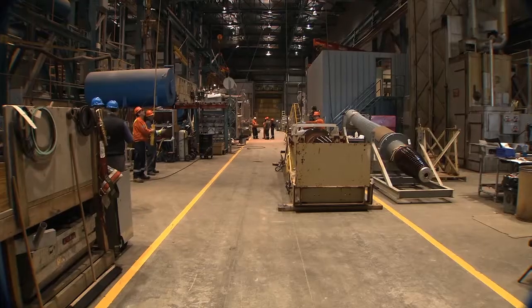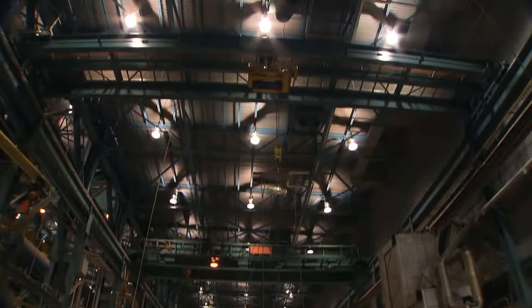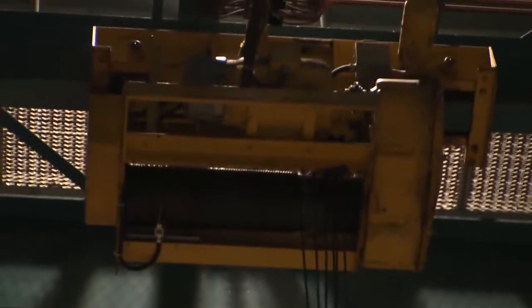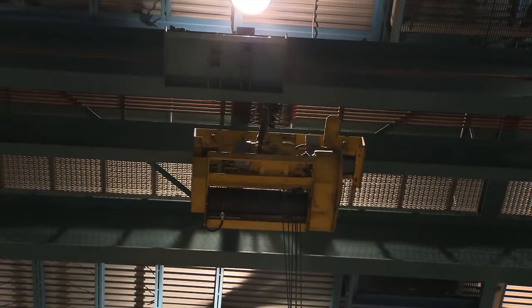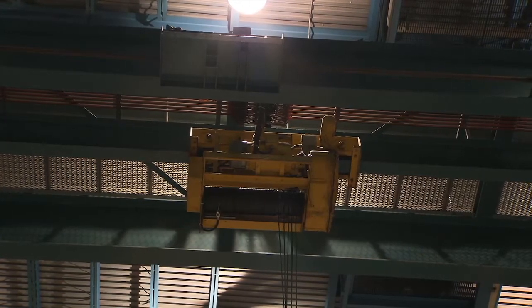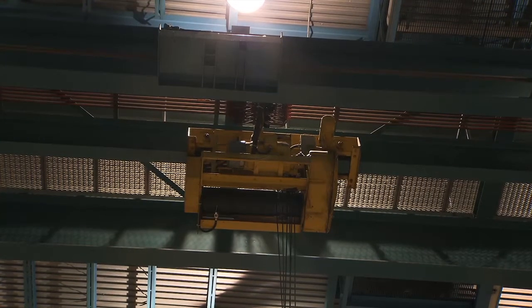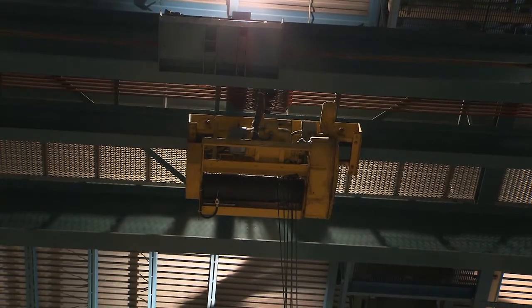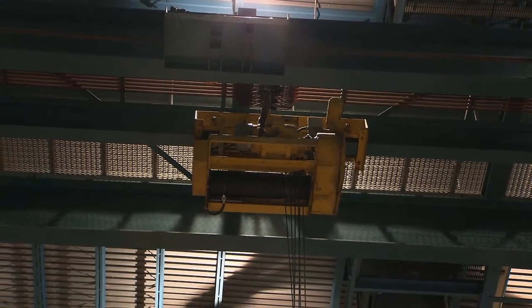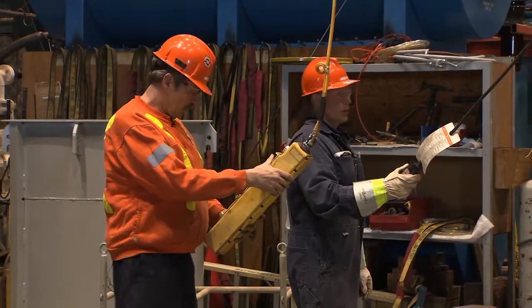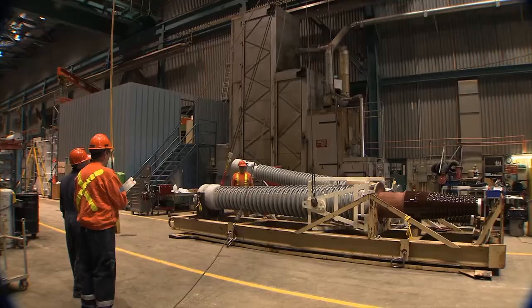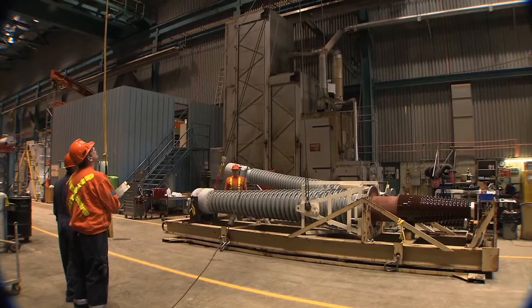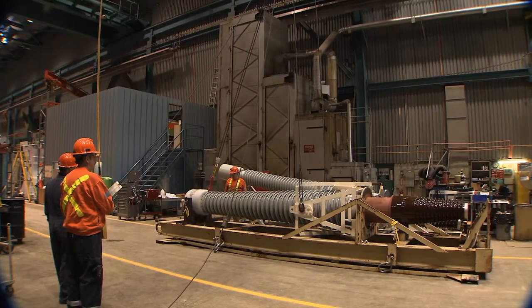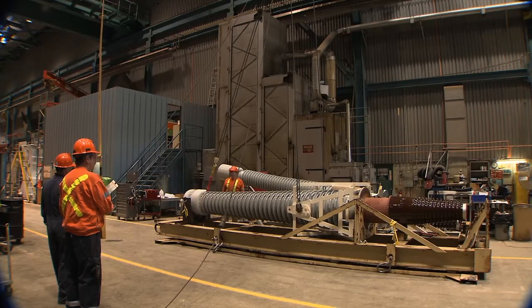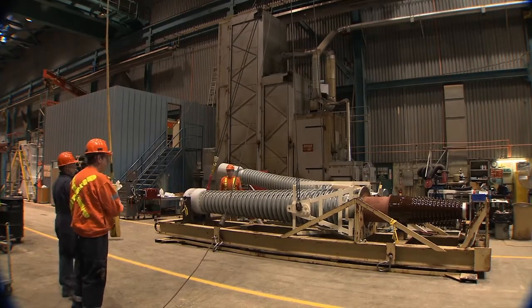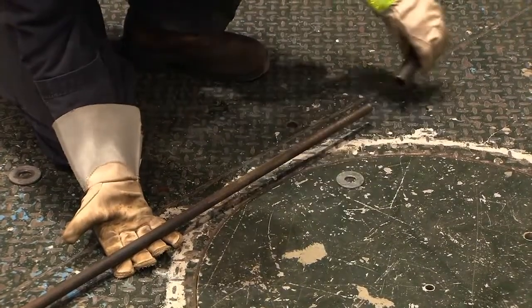The crane operator should make sure that the crane is positioned properly in conjunction with the bushing and lifting jig. This ensures that when the bushing is lifted, that it will be properly balanced and not sway. A separate operator using manual cable remote controls should control each hoist. The crane operators for the bridge crane and for the electric portable hoist should coordinate their actions by staying in close communication. Okay, whoa, that's it. I'm already up.